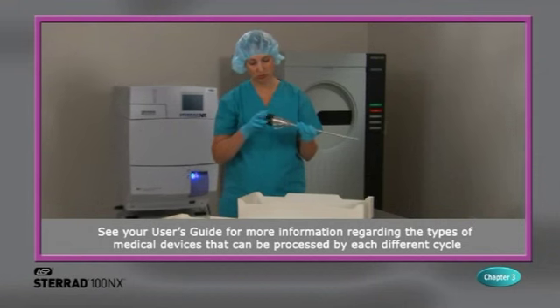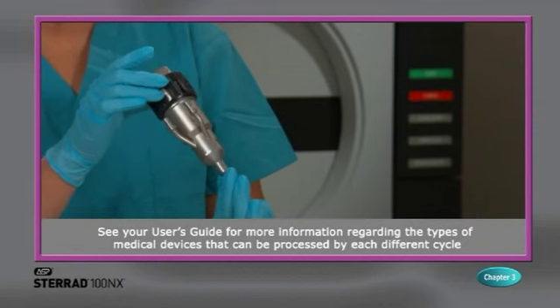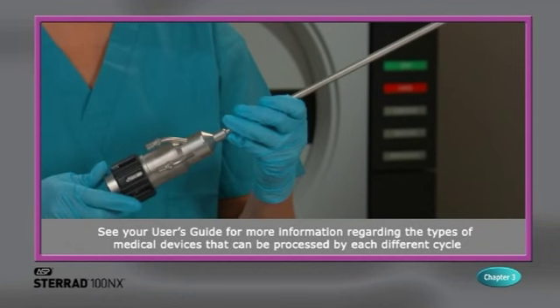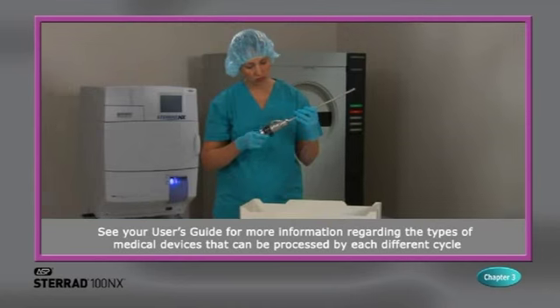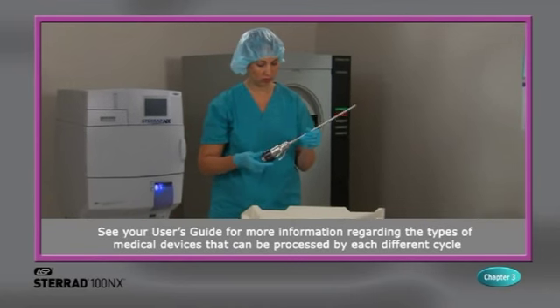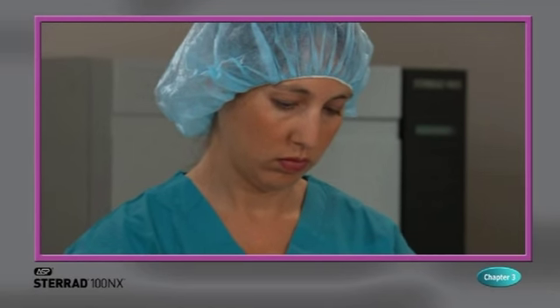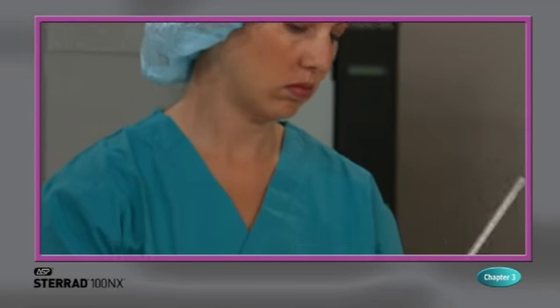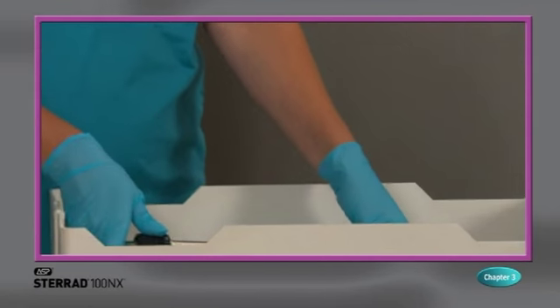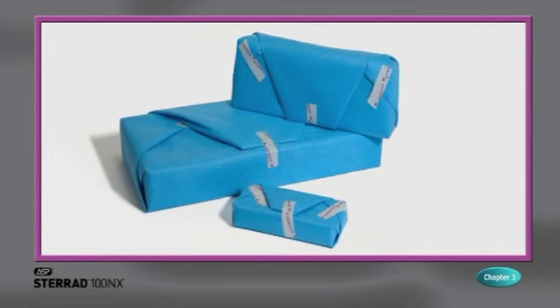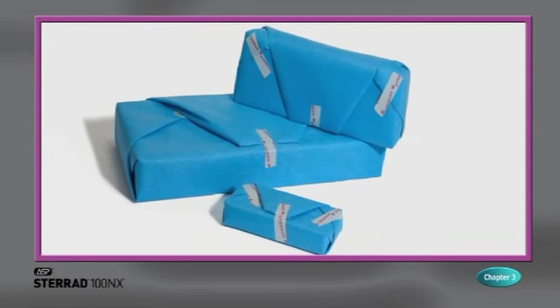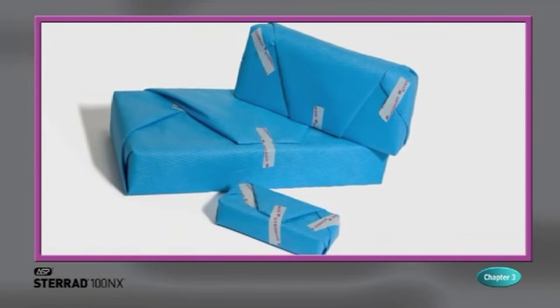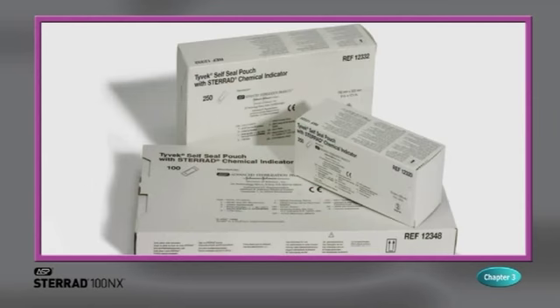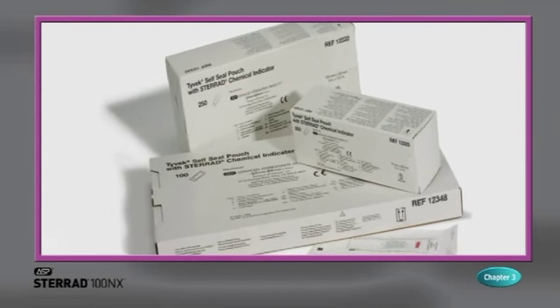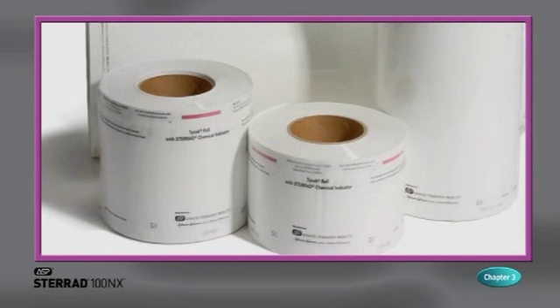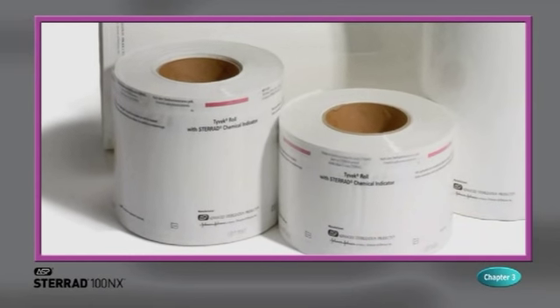All items must be cleaned, rinsed, and completely dried before being placed in the Sterrad 100NX sterilizer. Loads containing moisture may cause cycle cancellations. Carefully inspect all instruments and devices for proper cleaning and drying prior to packaging. Be sure to use only Sterrad system-approved instrument packaging. Approved packaging includes polypropylene sterilization wrap or Tyvek pouches and rolls with the integrated Sterrad chemical indicator strip.